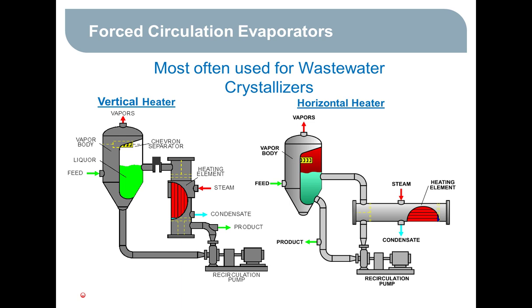The important thing in a forced circulation evaporator is that the heat exchanger is located below the level of liquid in the crystallizer vapor body. There's a level that's maintained in that vapor body. The crystallizer heater is submerged under that level. So the crystallizer heater body is flooded, and no evaporation occurs in that heater. All that happens is sensible heat is transferred. The evaporation occurs when the heated brine exits the heat exchanger and it flash boils when it enters the vapor body. So it's a flashing type evaporator, not a film type.